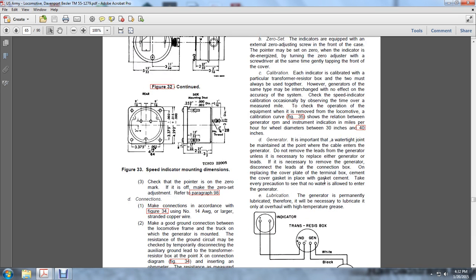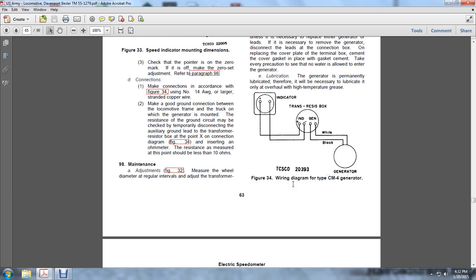The generator must have a watertight joint where the cable enters the generator. Do not move the leads of the generator unless necessary to replace the generator leads or to remove the generator. Disconnect the leads at the connection box. When replacing the cover plate of the terminal box, cement the cover with gasket cement. Take every precaution that no water is allowed to enter the generator. Lubrication. The generator is permanently lubricated, so it will be necessary to lubricate only at overhaul, using high-temperature grease.